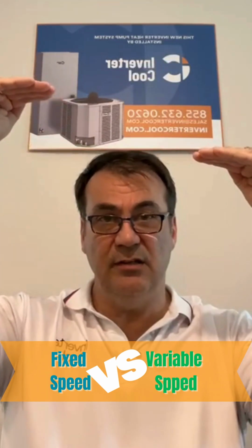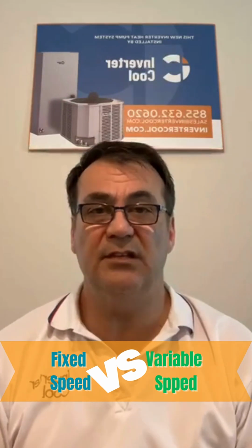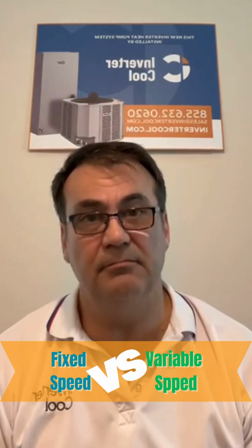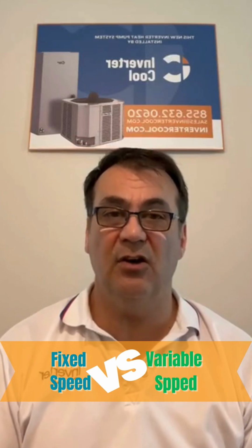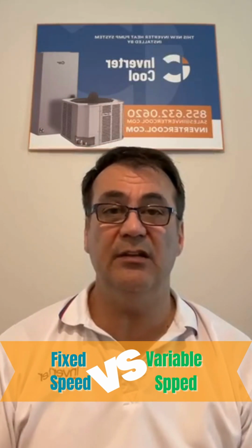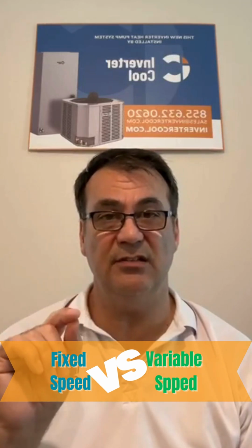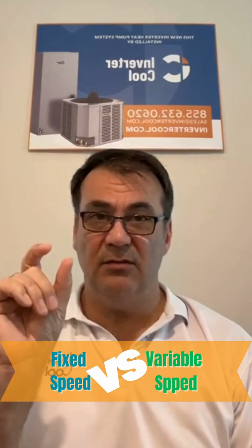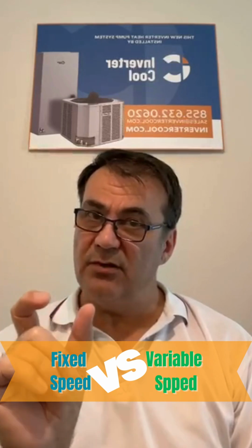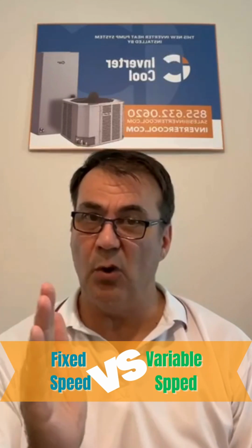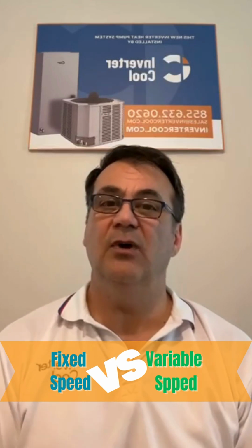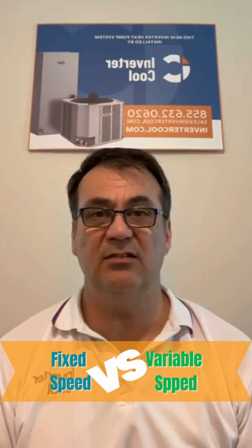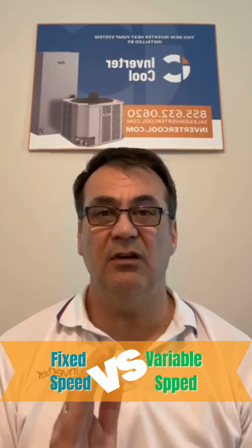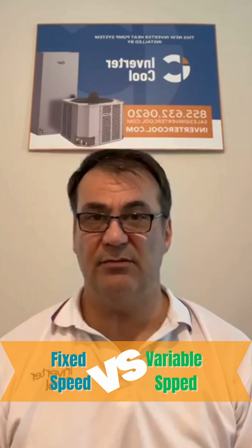You're going to have a higher energy bill with the fixed speed system or the 2-stage system because it's either on or off. And the way they do the staging on a 2-stage system is they put a little valve inside of the compressor to bypass a portion of its capacity while it's running in low speed. So the compressor is still at 100% speed or 0.